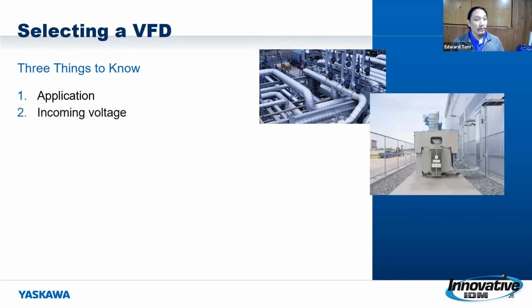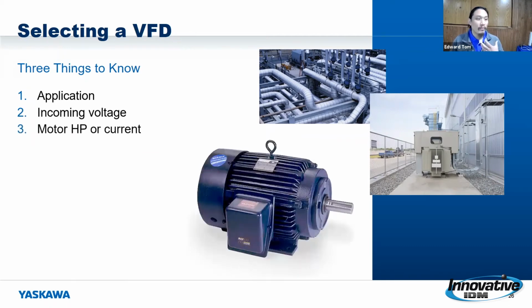The other is the incoming voltage. What's important is that that voltage will dictate what voltage drive you get. There is a distinct 200 volt class or 240 volt drives, there are 480 volt drives, and there are also 600 volt drives. So we do want to know the incoming voltage it's going to be wired to, so that we get you the correct drive the first time around. And certainly the motor horsepower or the current. If you've got either of those, that helps a great deal because the drives come in different sizes. So imagine a 1 horsepower drive: you can get a smaller drive compared to a 100 horse, 250 or even larger. It is going to be a different drive, so we want to get something tailored for that.